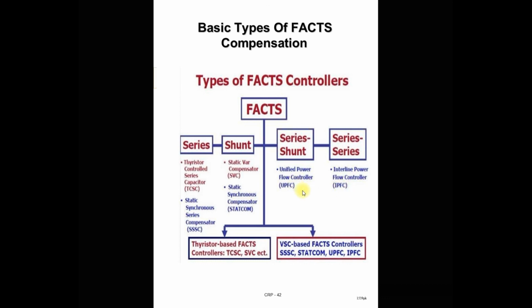Out of all these six FACTS controllers, two are thyristor based. The red marked TCSC and SVC are both thyristor based. It means the thyristor is used in these FACTS devices for the control of reactive power or voltage. The other four, SSSC, STATCOM, UPFC and IPFC, are voltage source converter based FACTS controllers.